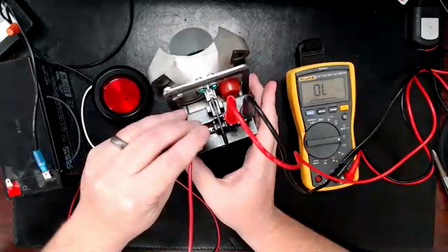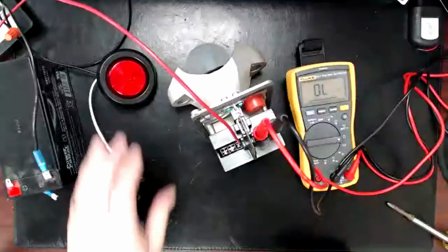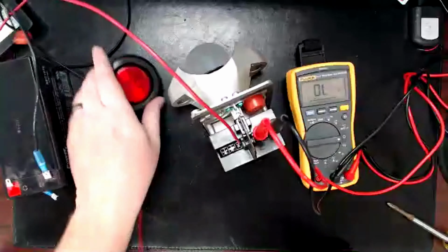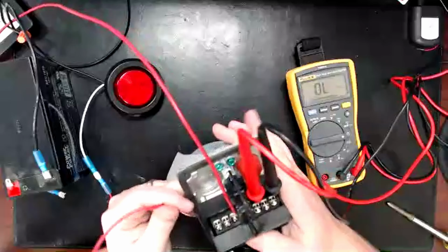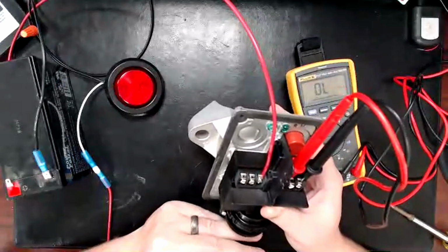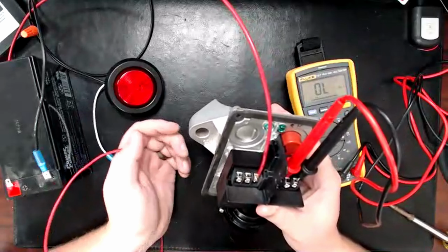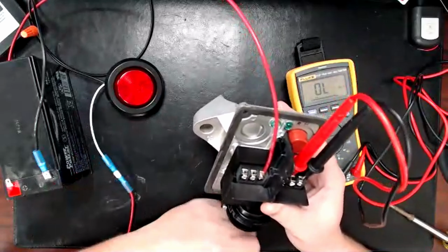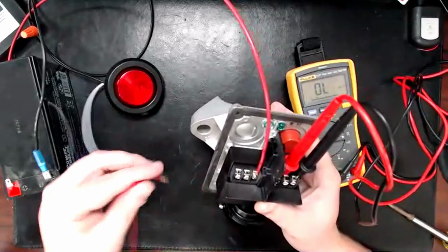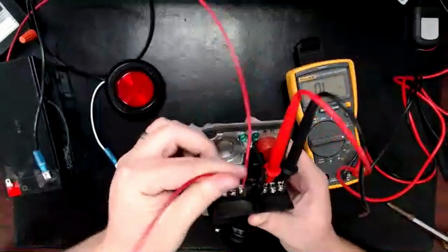And so for electricians, they would call this here the line, because that's your power bringing it in, and they'd call this side the load because it's what's putting the load on the circuit. So for my load side of it, I have to think about my sequence of operation. What do I want to happen with this? When do I want my bell to activate? Do I want it to be activated all the time and then get switched off? Or do I want the opposite? Do I want it turned off all the time, and then whenever it goes into alarm, I want it to turn on? Well, with a water flow bell, I always want it silent unless water's flowing. So I'm going to use the open set of contacts because open means turned off.